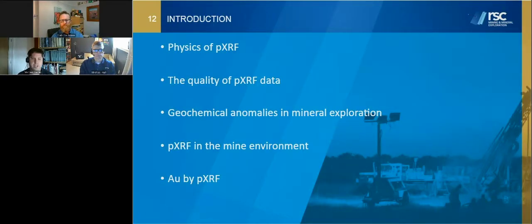I want to dive into the physics of portable XRF for a minute — X-ray physics more broadly — because we actually understand it really well and there shouldn't be any surprises. All the things that we see, as I'll show you some examples, we can model and we understand. The way X-rays interact with anything you put in front of an instrument, we have a pretty good idea how well that's going to work. When the data are collected with decent protocols, decent workflows, appropriate standards, and treated appropriately, you finish up with really nice comparisons to the lab.